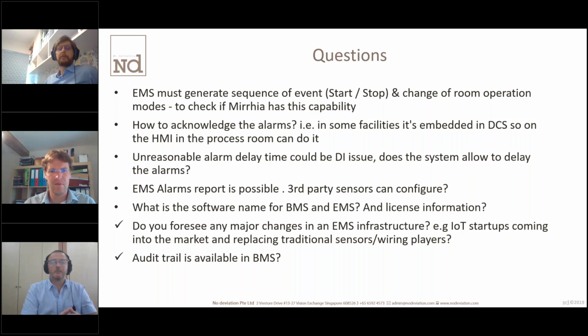Yeah. So for me, you need to address the root cause of why you are having alarms, and not create a longer delay. So definitely a good practice when you do your commissioning and validation is to ask, what is the science behind the delay of the alarm, and is that reasoning in line with our process tolerance? That's what we need to do when we configure and validate the system. So that is part of what we do when we do the commissioning of the system anyway. We fine tune those parameters so that we know what the minimum time should be.